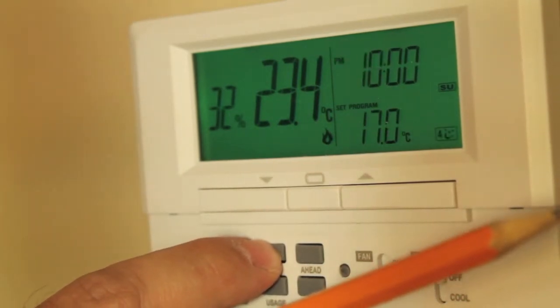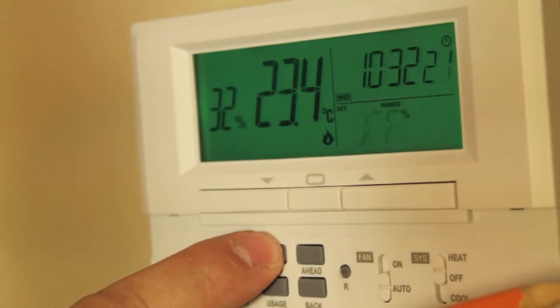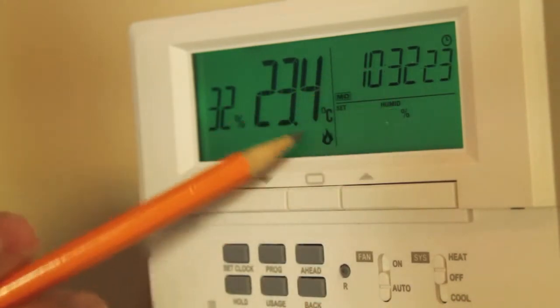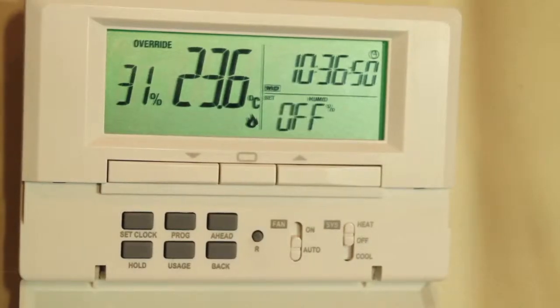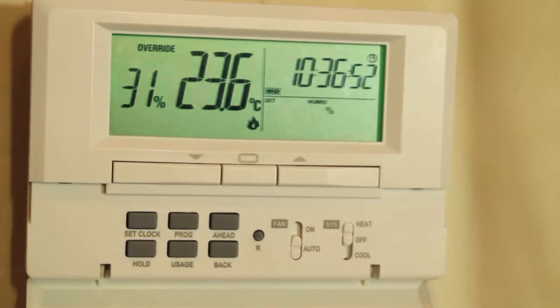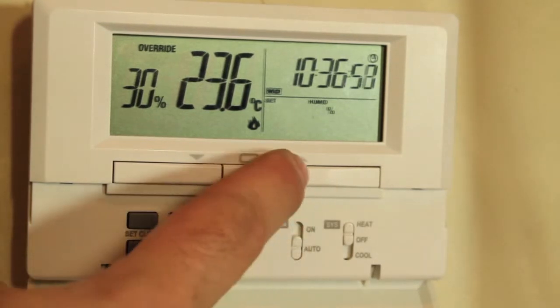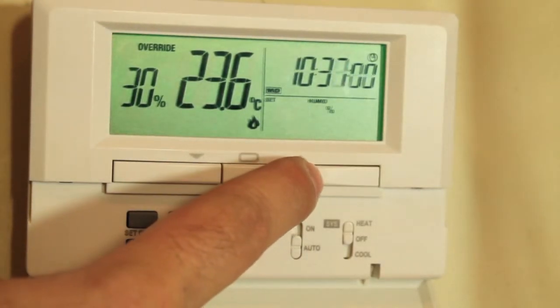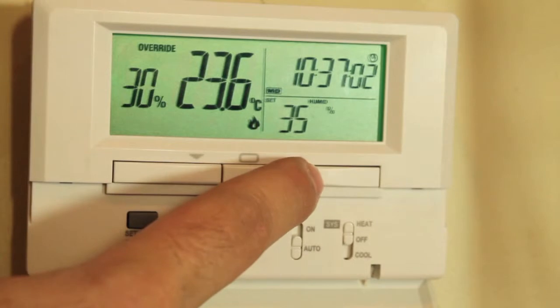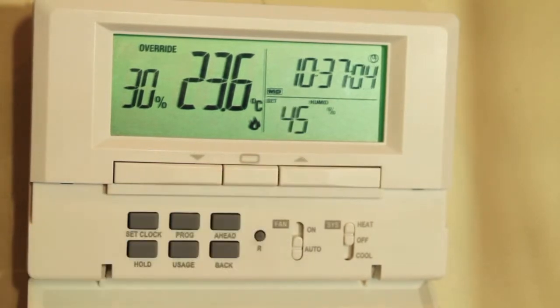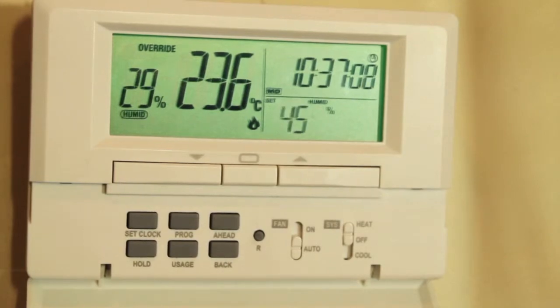After program four for Sunday you will then see the word off. This word off represents the humidity setting for your humidifier. It will only show if you're on the heating setting. By pushing the up arrow button you can change the percentage humidity you want for your home. This will only have an effect if you have attached humidifier wires to the H1 and H2 during installation.